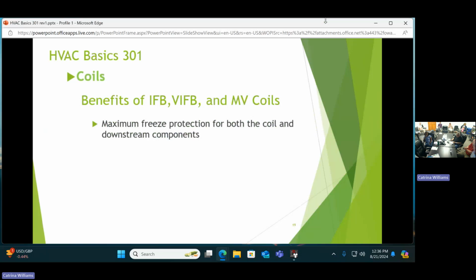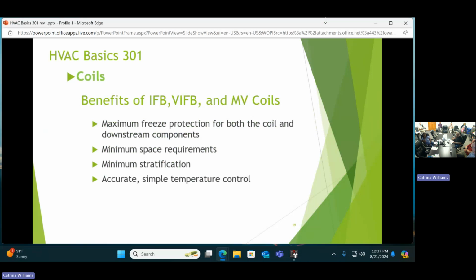So what are the benefits of IFB? Maximum freeze protection for both the coil itself and downstream. As Doug pointed out in those drawings, minimum space requirements. For the air handler manufacturers that are using these coils, that's big because it saves box size, it saves roof curb mounting, whatever it might be. Minimum stratification, so you don't have those hot and cold bands going through the area. And we have an accurate, simple control system.